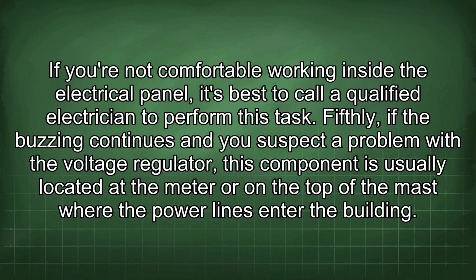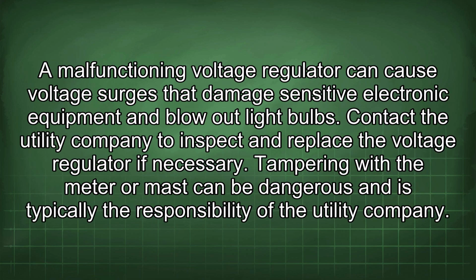Fifthly, if the buzzing continues and you suspect a problem with the voltage regulator, this component is usually located at the meter or on the top of the mast where the power lines enter the building. A malfunctioning voltage regulator can cause voltage surges that damage sensitive electronic equipment and blow out light bulbs. Contact the utility company to inspect and replace the voltage regulator if necessary. Tampering with the meter or mast can be dangerous and is typically the responsibility of the utility company.